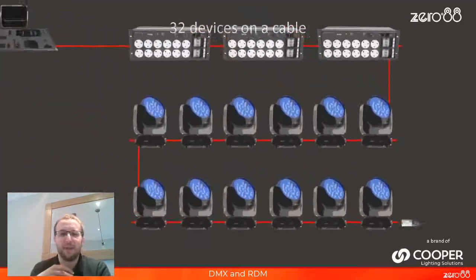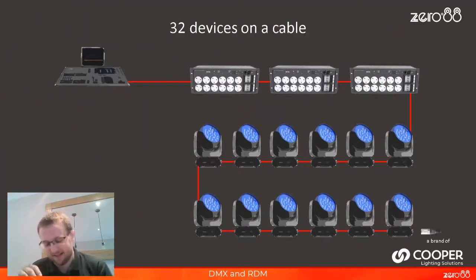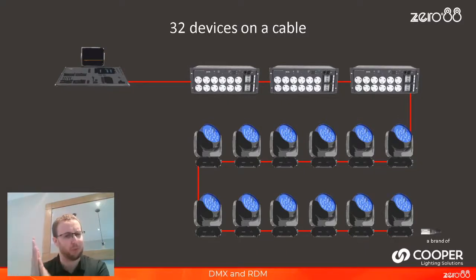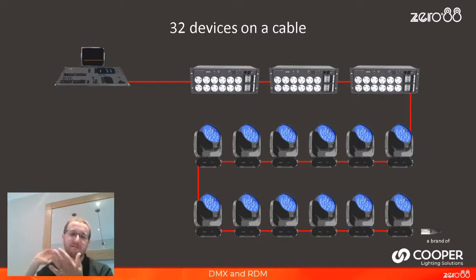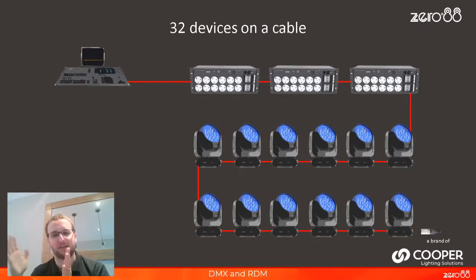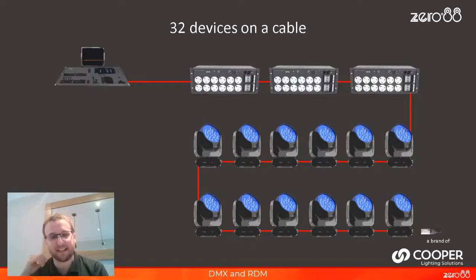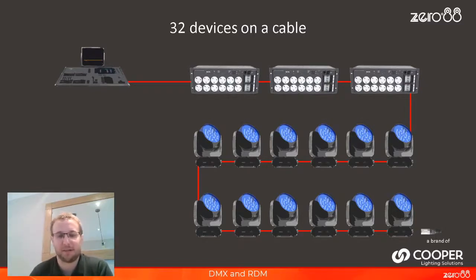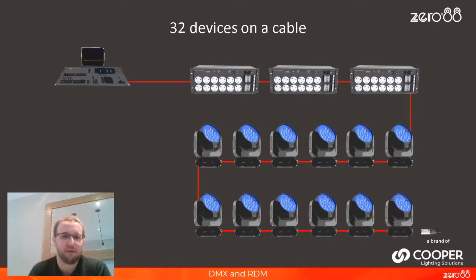Officially you do have to have a DMX Terminator. It stops what are called reflections — if I ran into a brick wall, I'd bounce back; but with a mattress gaffer-taped to the wall, it softens the blow. The DMX Terminator does that: it stops reflections down the line, which can cause the last couple of moving lights to get confused. Lots of us run DMX setups without Terminators and it's probably fine, but when you get into RDM, the Terminator becomes more crucial. I strongly encourage you to use DMX Terminators.